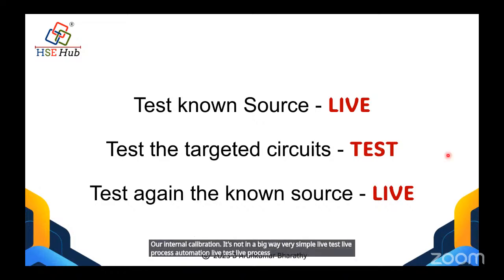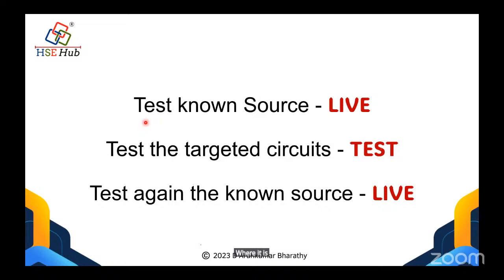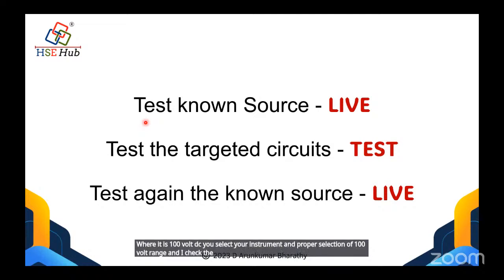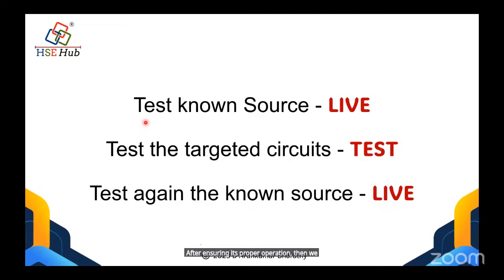First, we have to test the test and measuring equipment with a reference voltage, which is 100 volt DC. You select your instrument, make the proper selection of the 100 volt range, and check the reference voltage. If it shows 100 volts, then yes, my instrument is perfect. If it shows more than 15% deviation, something is wrong. That may be the probe, or maybe the battery, or some other thing. After ensuring its proper operation, then we measure where it has to be tested.